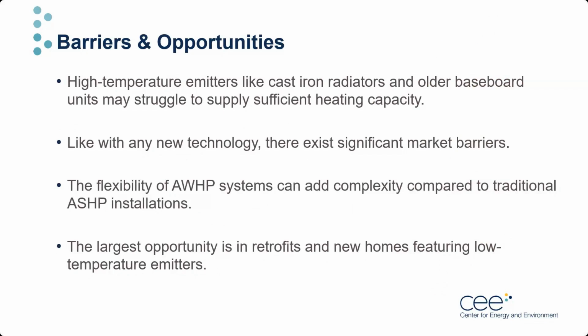As air-to-water heat pumps are a new technology to this market, barriers like limited workforce experience and a lack of standard rating methodologies will still hinder adoption. Although they are like other air source heat pump systems, the flexibility of air-to-water systems to work in many system configurations poses additional complexity and often requires more design work than boilers or even air-to-air alternatives. Air-to-water heat pumps have current opportunities in retrofit or new construction homes that feature low-temperature emitters such as radiant slabs or panel emitters. And additional opportunities for applications will still develop alongside familiarity with the technology. Next slide.